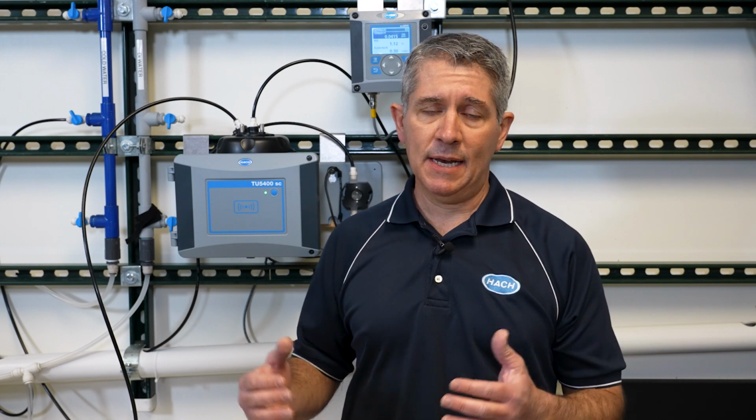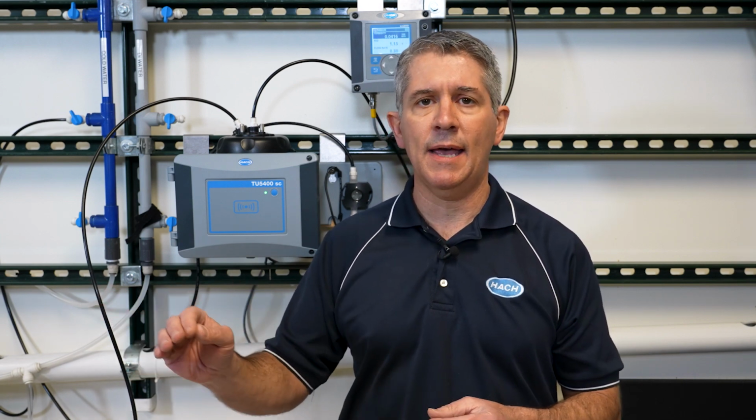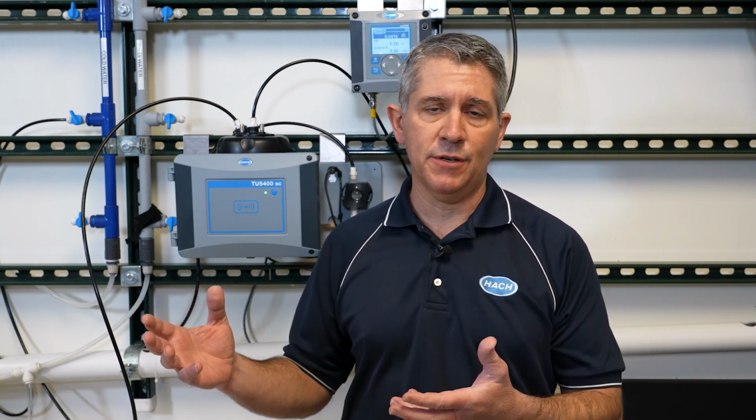So what we're going to do is show you how to plumb this and set it up to minimize the bubbles. I should also say that it may not completely get rid of the bubbles. It may, but there may also be some management that has to happen on the SCADA side. So you can put in a little bit of a delay on your SCADA system, so when you're not producing water anyway and bubbles enter the turbidimeter, you're not having any problems.